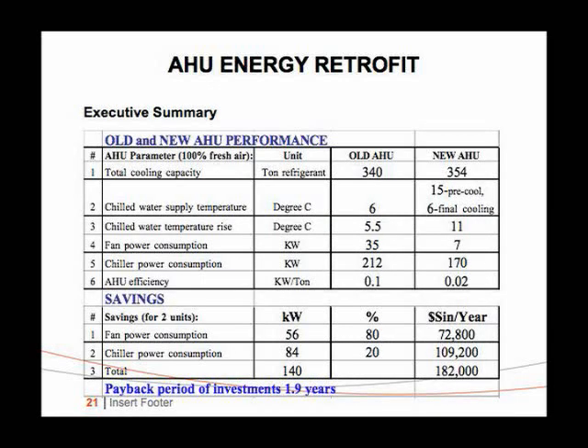And a little summary. Old air handler, 340 tons. The replacement is 354. AHU efficiency in terms of kilowatt per ton, because this is servicing outside air at a wet bulb design of 27 degrees C. So there's a 5 times drop in kilowatt per ton. Payback in 1.9 years, and this is in the year 2000. So with today's rates, it would be less than 1 year.